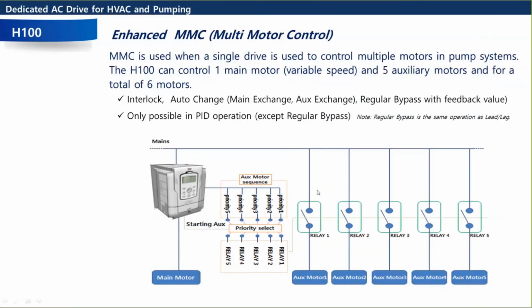They really like it. It's pretty cost effective because you only need one drive and some contactors and overloads here. So you could have interlocks on here that'll enable or disable the system. Auto exchange, which is like an alternation kind of deal. There's some bypass features in here that you could be triggering based on a feedback value. And yeah, this is all PID related. So you have to be running PID to be using this multiple motor control.